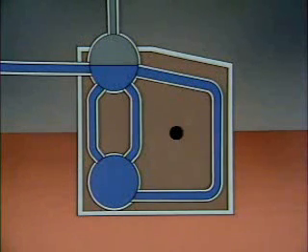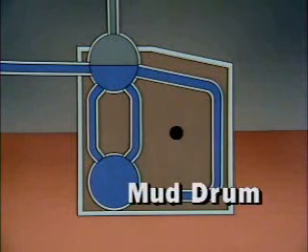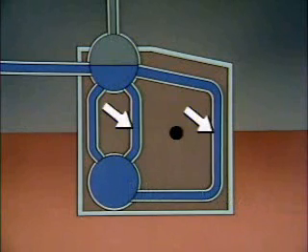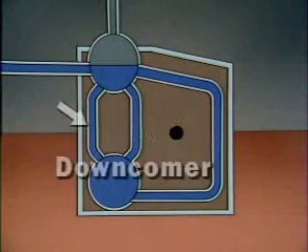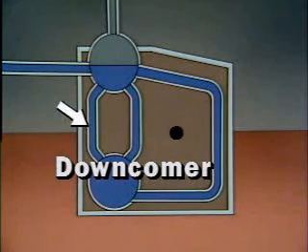And the lower drum is often called a mud drum. There's also a series of water tubes called risers, which carry a steam-water mixture to the steam drum. And this one has a downcomer, which carries water from the steam drum to the mud drum.